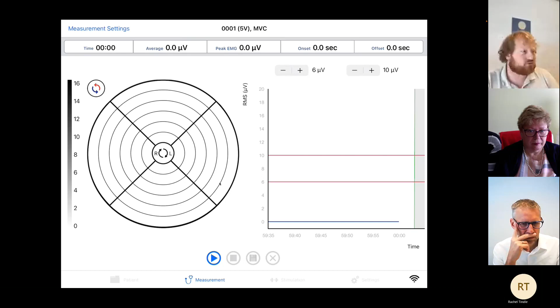On top of the line graph, you have 2 plus and minuses, and this is actually to set the reference lines. So if I press them, you see a red line coming into the screen. And these can be modified during measurement as well. And this can be used for a number of things. So it can be used during a biofeedback session that you say to the patient, please keep the contraction above this level, or try to have a multiple MVC measurement, try to reach this level. But it can also be used for yourself during treatment. So because now the line graph only shows 30 seconds, the first contraction after 30 seconds is out of the image, and you can use reference lines to set the height of that contraction when it disappears from screen.